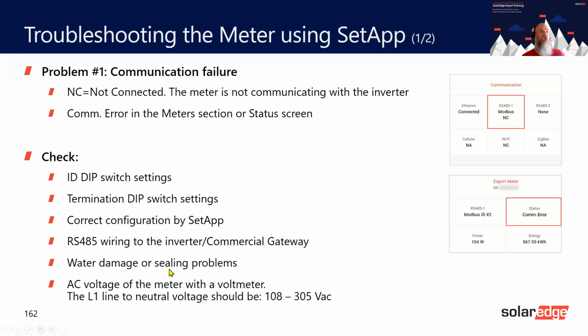You could look for water damage or sealing problems, but I doubt that will be one of the most common ones. That's a very, very rare one, especially if it's inside. It's not really going to suffer from water damage as such. And then the last one, to check that L1 has a voltage on it. Why L1? Because L1 is the connection that the meter gets the power from. So if you have lost a phase, if you've lost L1, then there's a good possibility that the meter won't work.